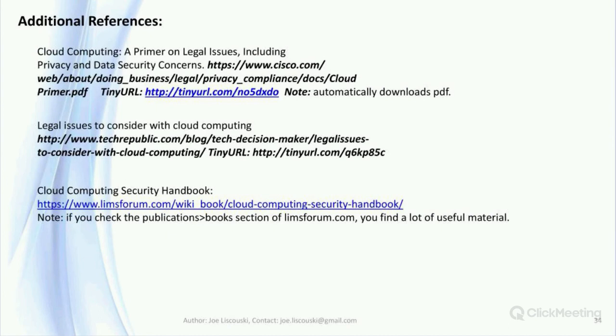One last pre-submitted question: how realistic is it to want to connect instruments to a remote database system from the lab? There is a distinction between the instrument — which provides an analog output — and the computer system. Often when a salesperson sells you an instrument they automatically sell you the computer as if they're the same thing. You don't connect instruments' analog output to remote computers — it simply doesn't work. What you really do is communicate via file sharing between the computer attached to the instrument and a remote computer. When you talk to a salesperson about connecting an instrument to your LIMS or remote ELN, what you're really doing is a computer-to-computer connection, not the instrument itself.